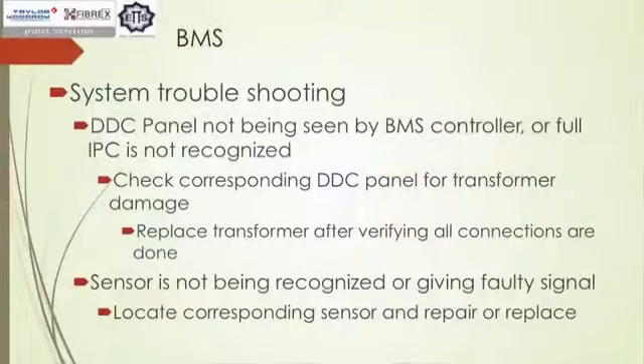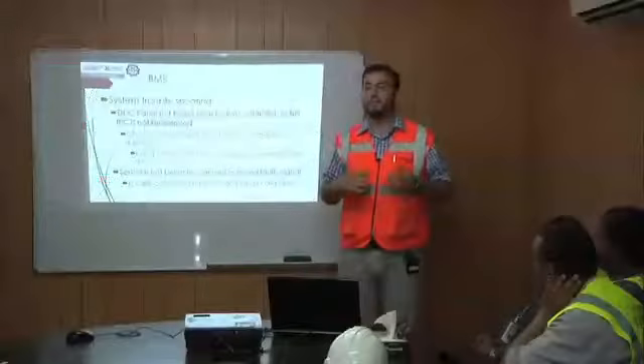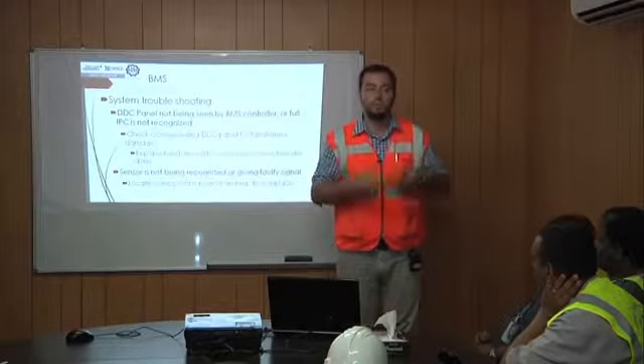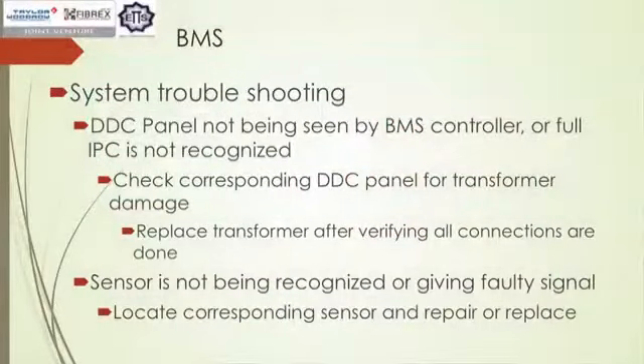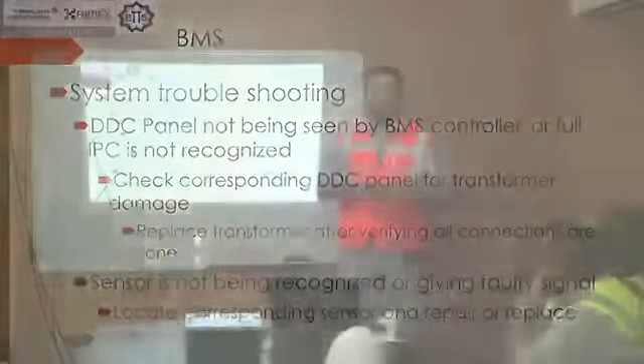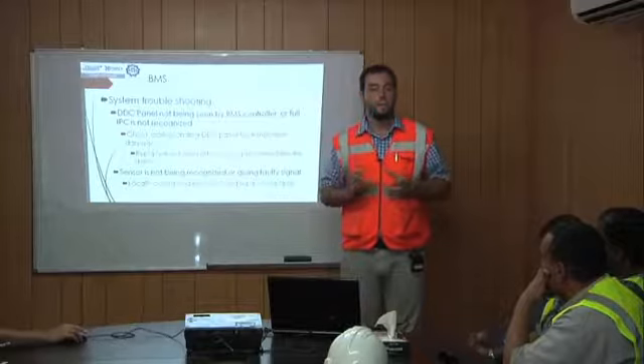Let's talk a little bit about the troubleshooting. So let's say the DDC panel is not seen by the BMS. We're sitting in terminal 3 and we cannot access, let's say, these 2 RTUs. It's giving us an error report. That could probably be the DDC panel transformer that we need to go and check. The whole panel is 24 volts energized, and if there was a power surge or inconstant power, this transformer, there are about 3 or 4 in every single one, maybe one of them got damaged, we need to take it out and replace it.